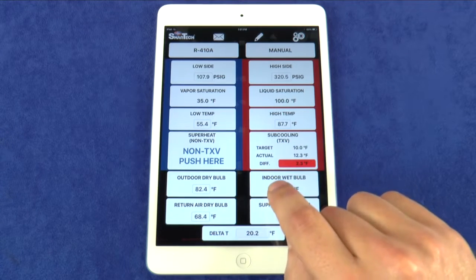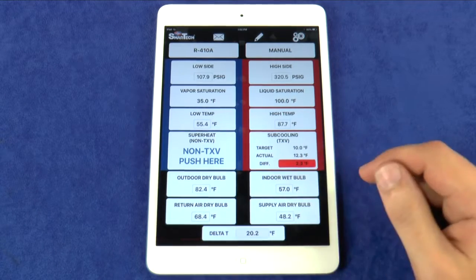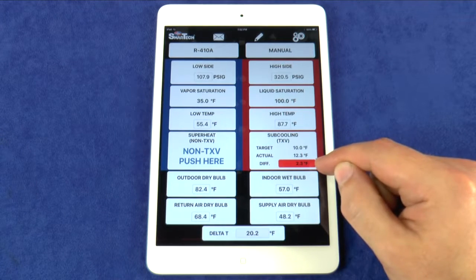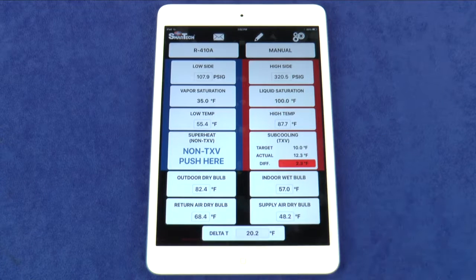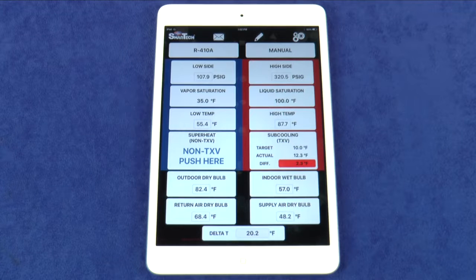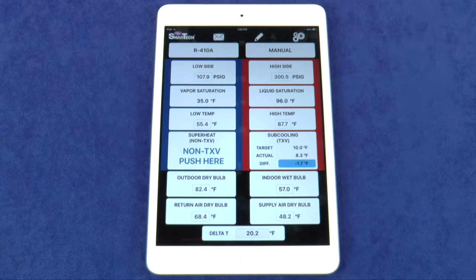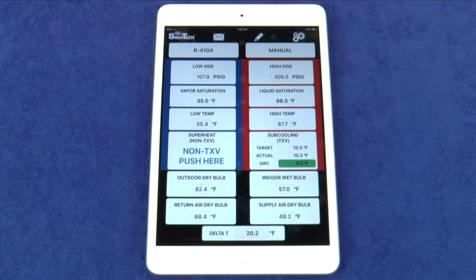This field features the Smart Charge Zone. The difference between the target and actual superheat or subcooling is shown here with color indicators. For example, I've set the subcooling target at 10, and as I change the value for the high side pressure, you will see the color indicator change. Red means the system is overcharged, blue means it is undercharged, and green means the system is properly charged.